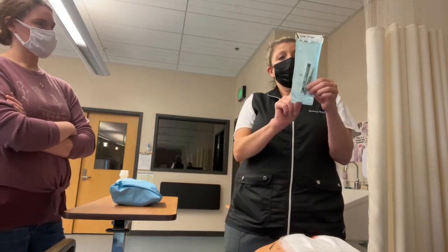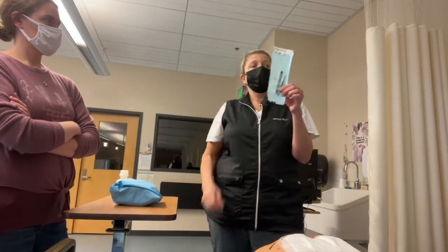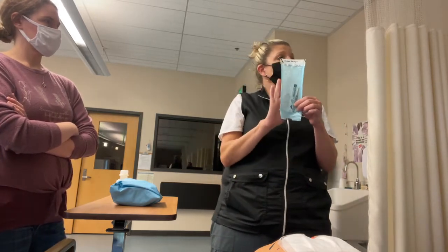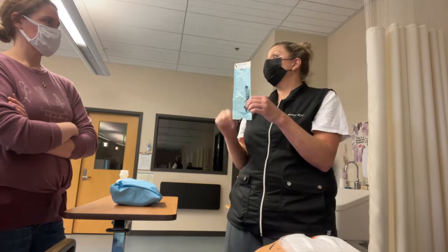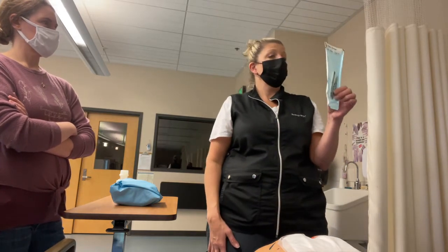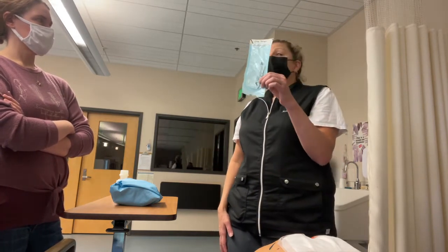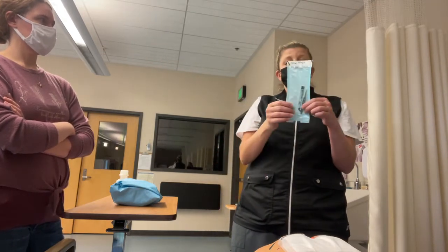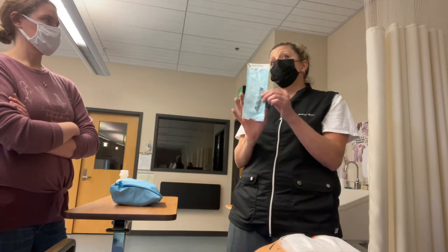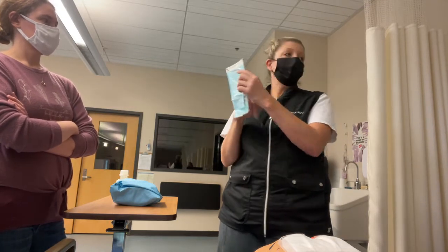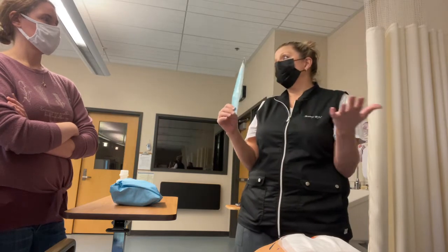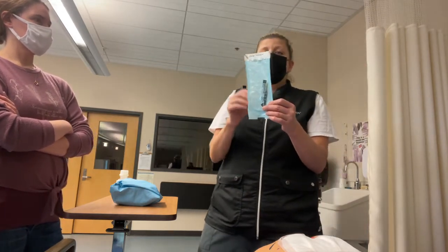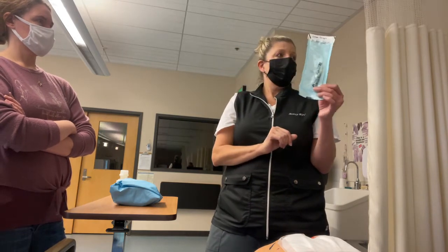3M, who did our sterilization packages, their manufacturer guidelines say that as long as the packaging is not compromised, there is no expiration date on a sterile bag. The facility that I worked at, just because of how much we're in and out, I said we're only going to use these for a year. So once a year was up, we needed to rewrap these. So just know what your facility's policies are. We always did a double check on all of our bags.